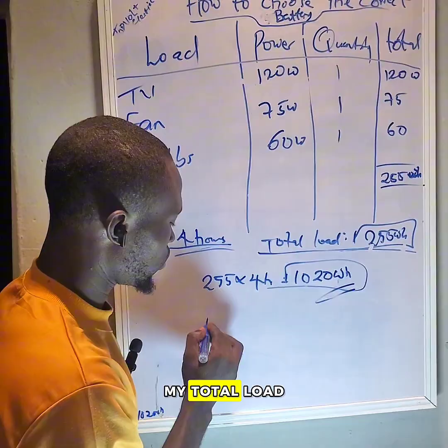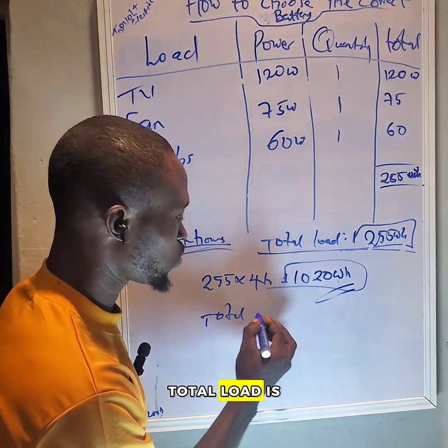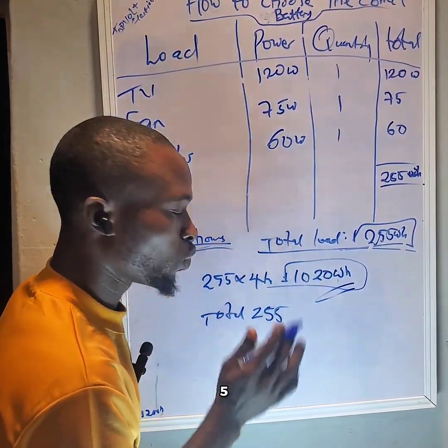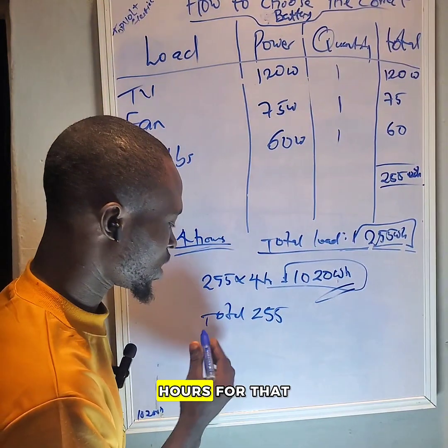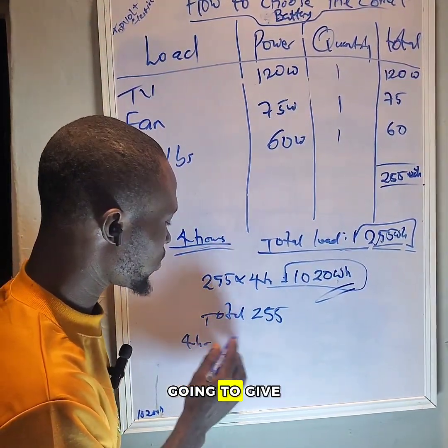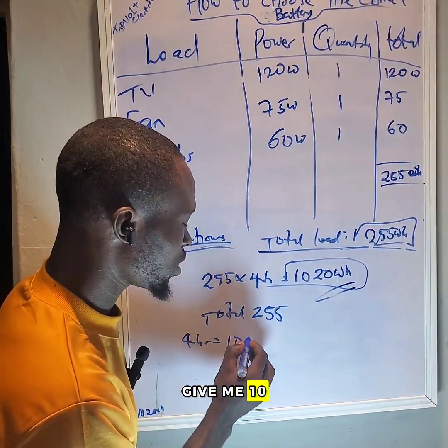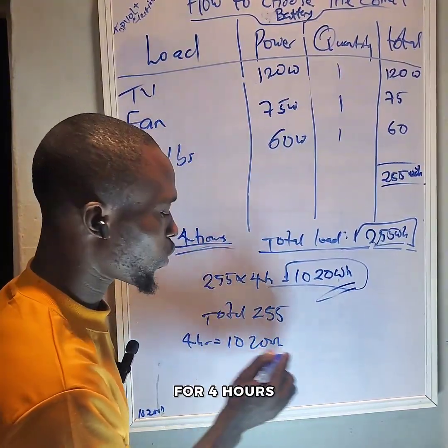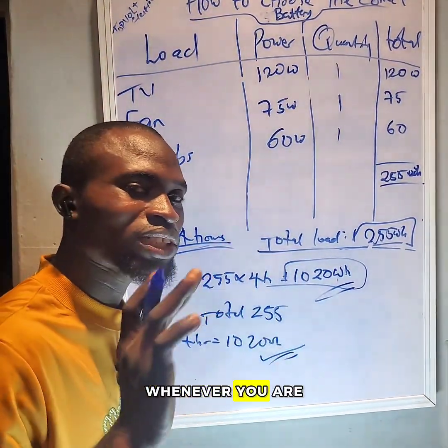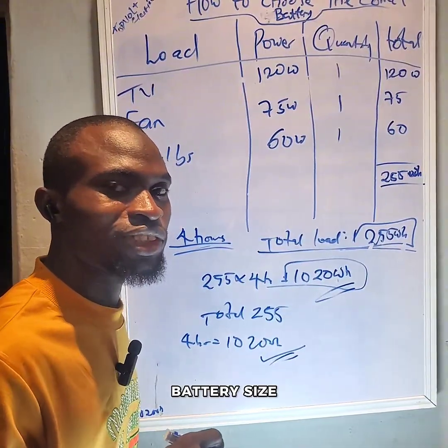So this is my total load, producing 255 watt hour. But if I multiply by 4 hours, for that 4 hours it's going to give me 1020 watt hour. You need to know this whenever you are sizing the correct battery size.